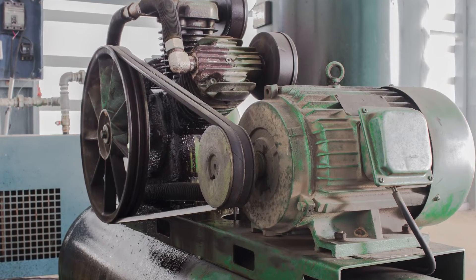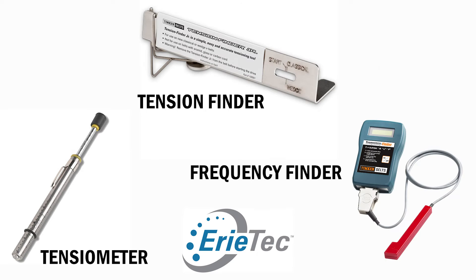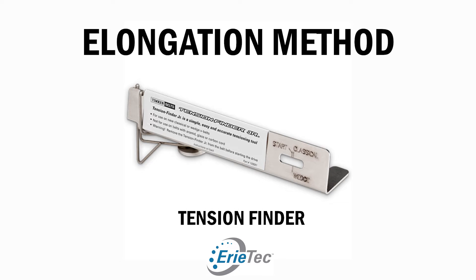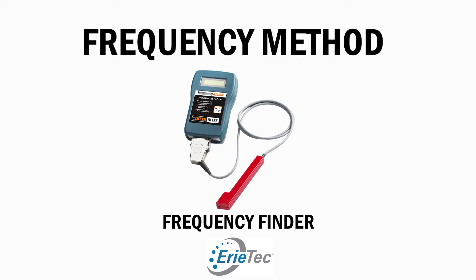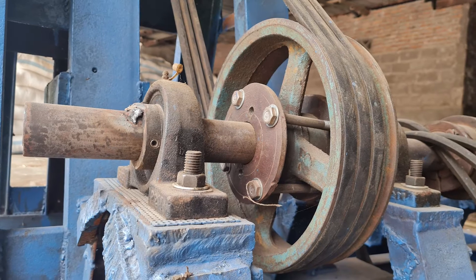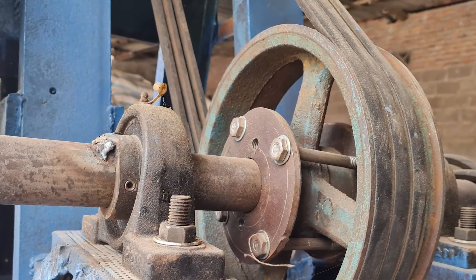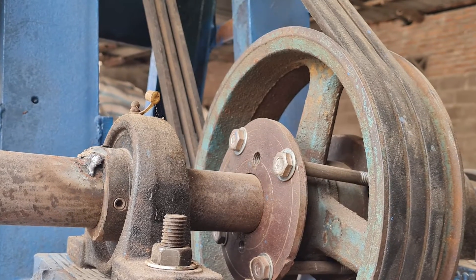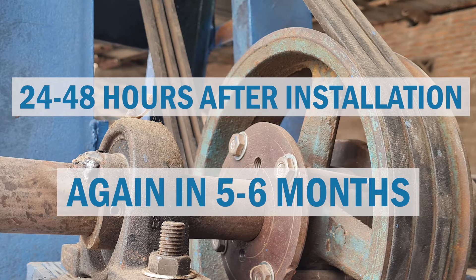Proper tensioning requires not a thumb test, but a tension checking device at installation. My thumb pressure, your thumb pressure, and the thumb pressure of those around us are all different. In the pictures, there are a couple of different pressure checking devices: the elongation method, which is a tension finder; a deflection method called a tensiometer; and a frequency method, which measures the frequency as a belt runs. A survey of belt manufacturers reveals that under-tensioning is a major cause of belt drive problems. Belts must be properly tensioned at installation, and because they're made of rubber and they stretch, tension again 24 to 48 hours later, then check the tension again in another five or six months.